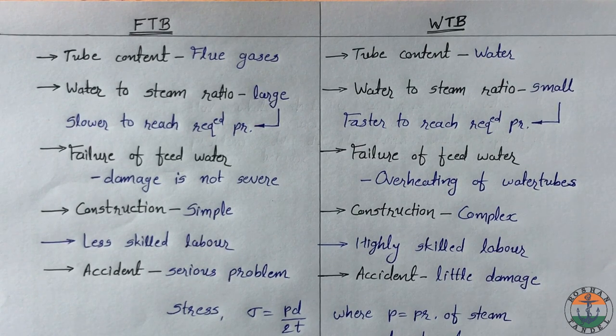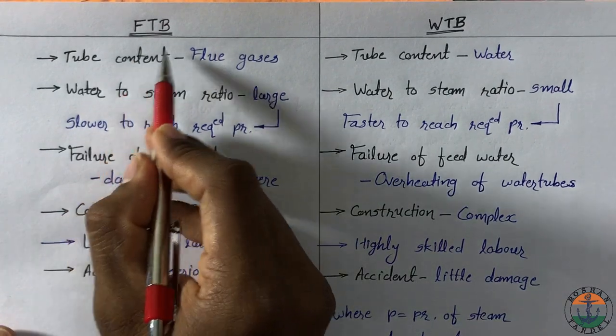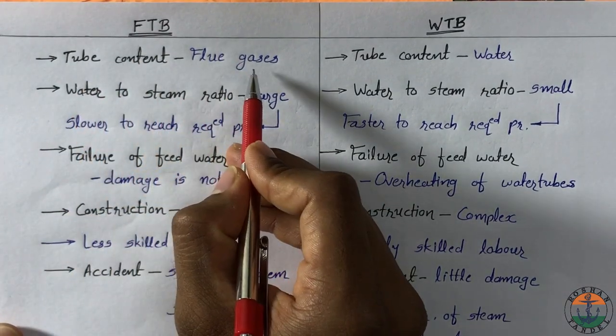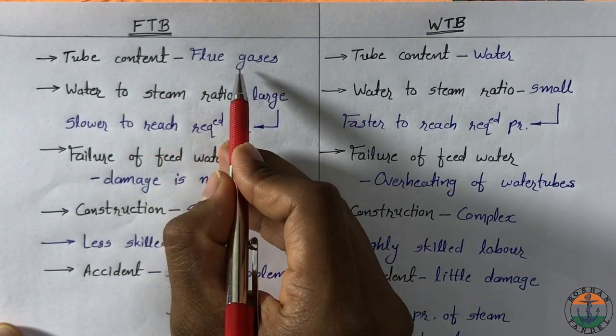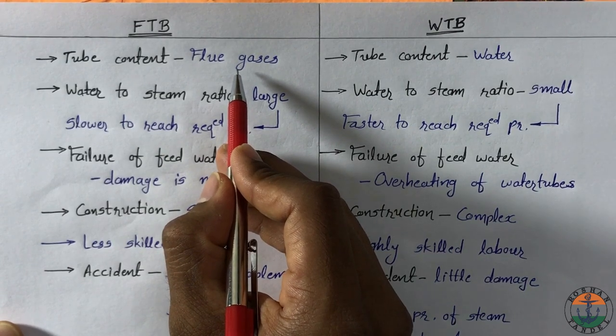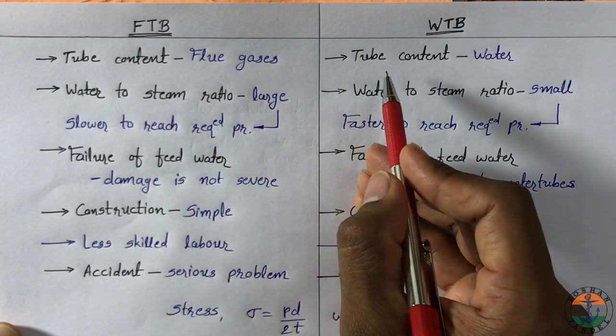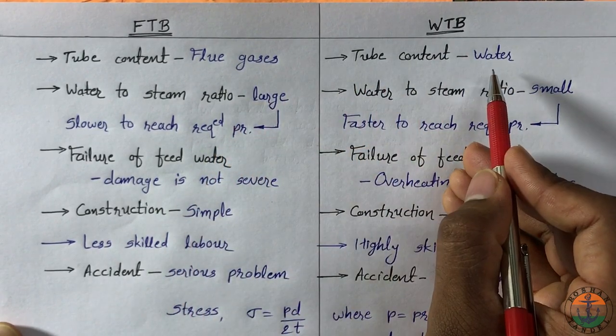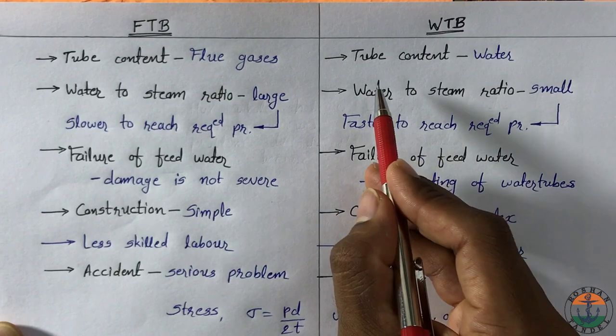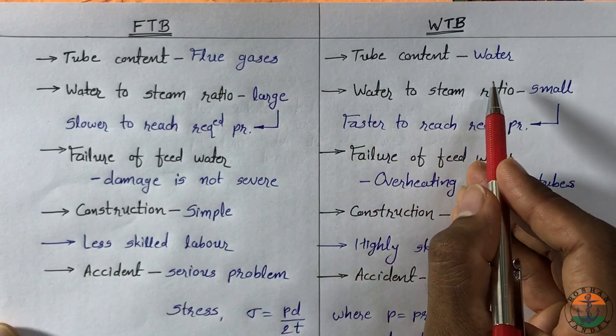There is a difference between fire tube boiler and water tube boiler. Fire tube boilers have products of combustion which means flue gases passing through the tubes. And these tubes are surrounded by water. In water tube boiler, water is flowing through the tubes. And these water tubes are surrounded by hot flue gases.